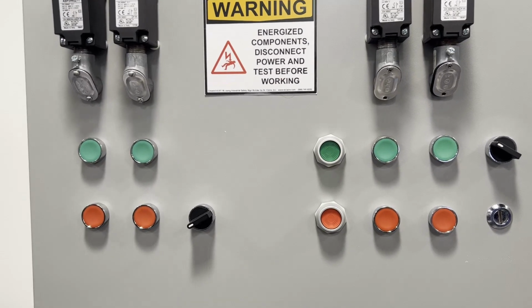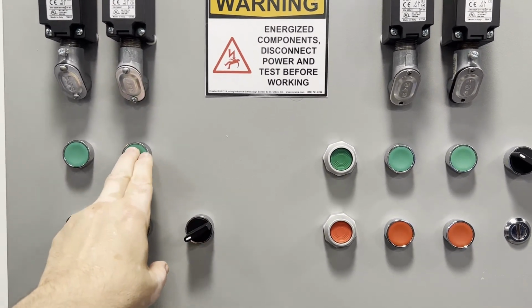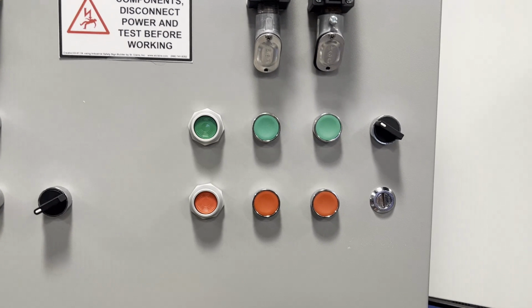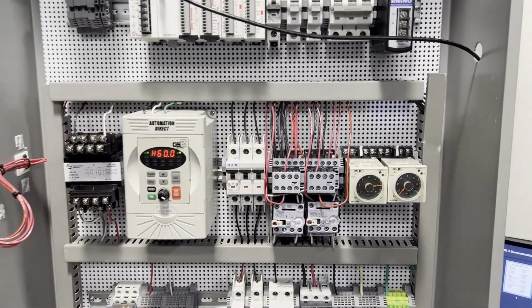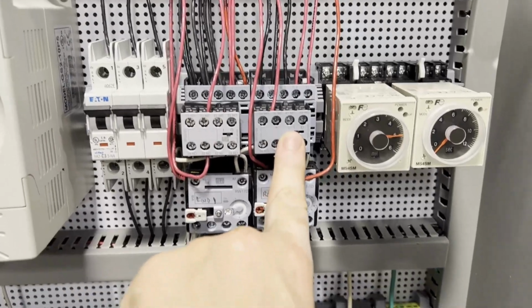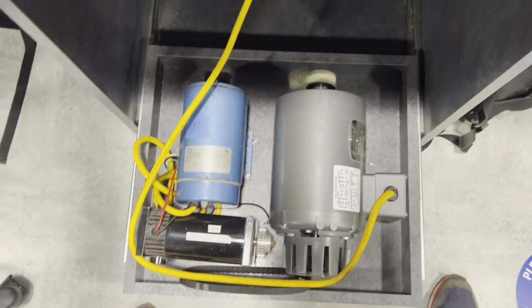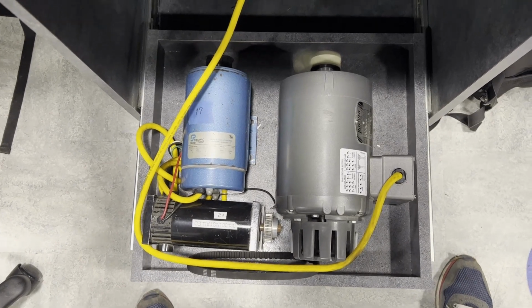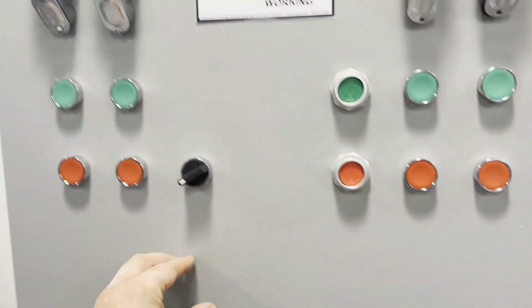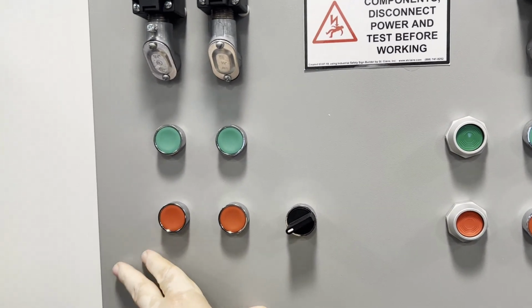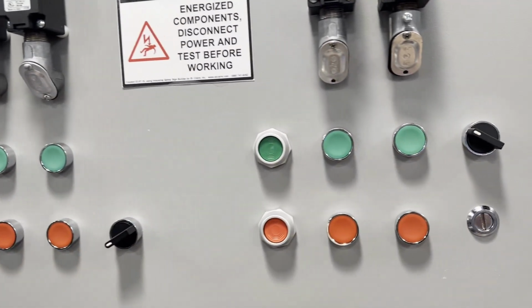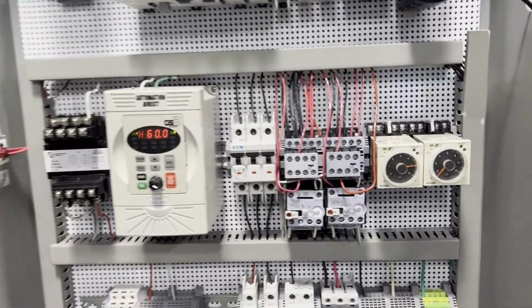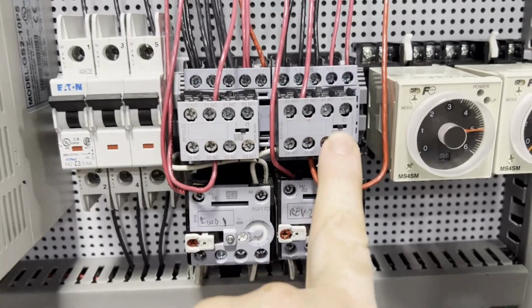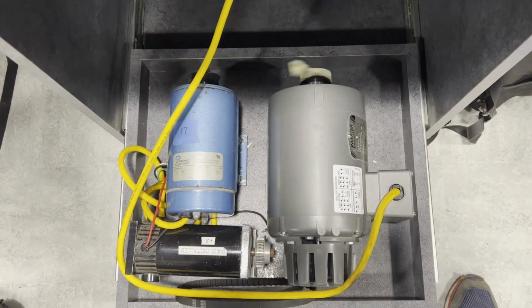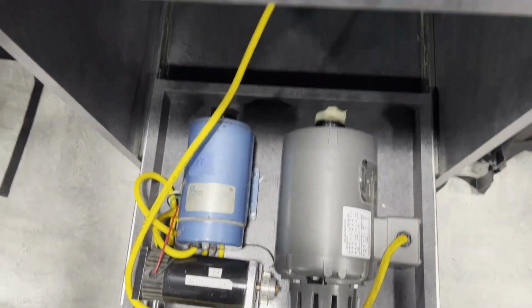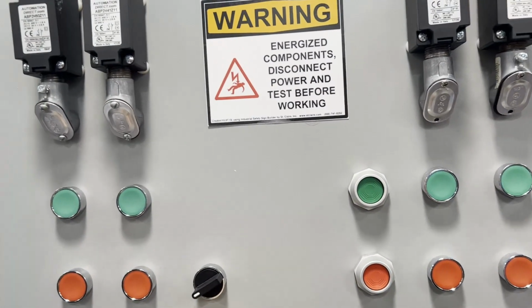Test number 2, reverse and stop. Start out pushing the reverse button. I hear a click and I hear the motor start. Verify. Reverse contactor closed. Motor is running in reverse direction. And then we push the stop. Contactor open. Sounds like motor is coasting down. Verify. Reverse contactor open. And motor coasting down in reverse direction. This concludes the reverse stop test.